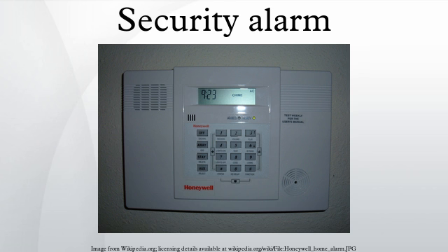There are also systems that permit a duress code to be entered and silence the local alarm, but still trigger the remote alarm to summon the police to a robbery. Fire sensors can be isolated, meaning that when triggered, they will not trigger the main alarm network. This is important when smoke and heat is intentionally produced. The owners of buildings can be fined for generating false alarms that waste the time of emergency personnel.